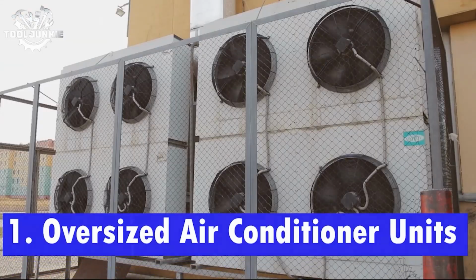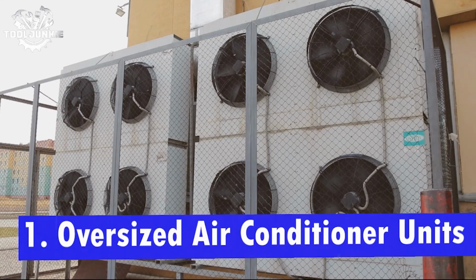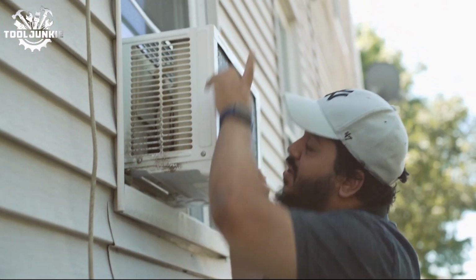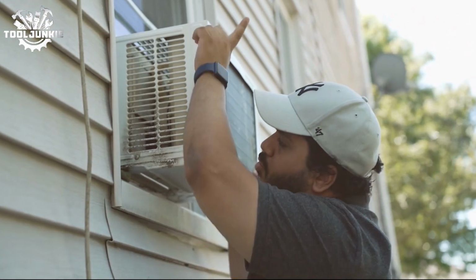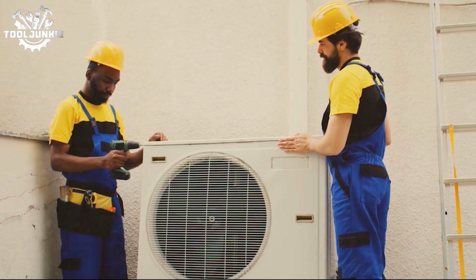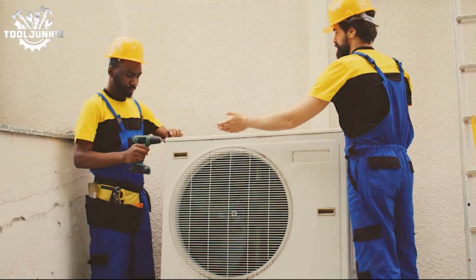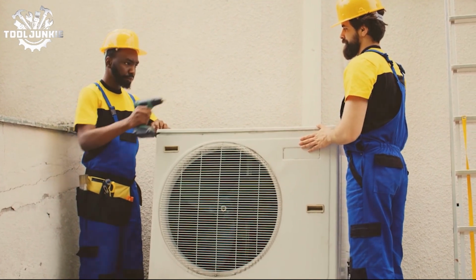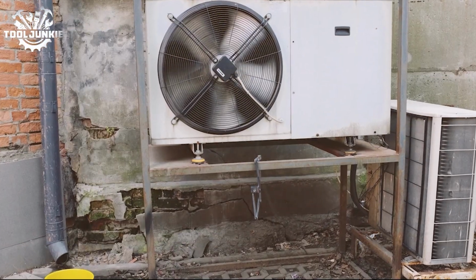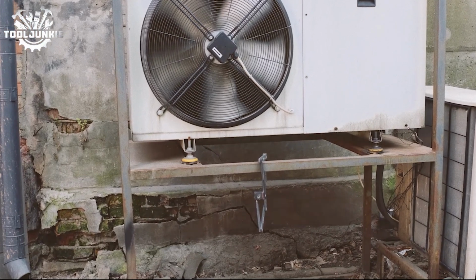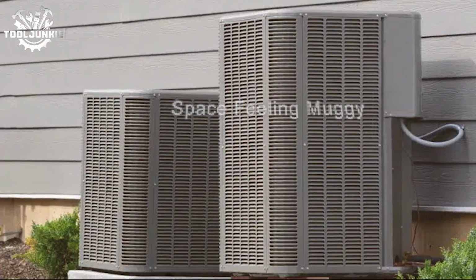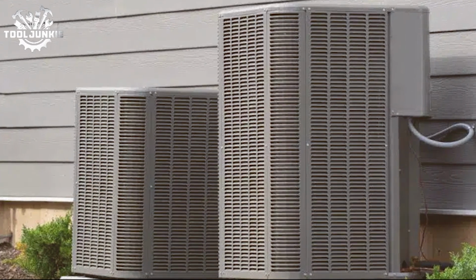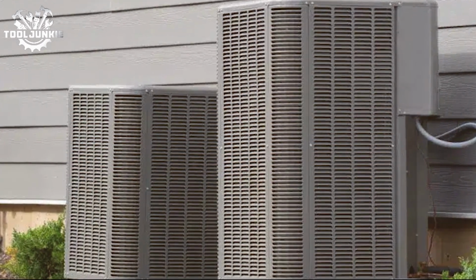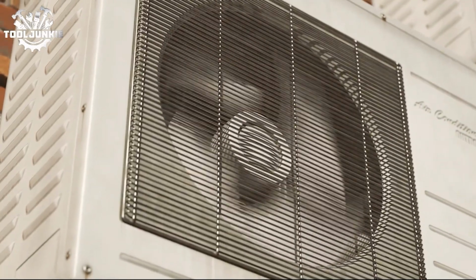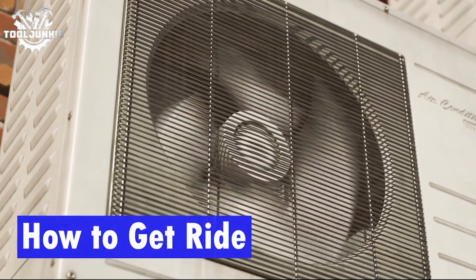Number 1. Oversized air conditioner units. First on our list of usual suspects is the oversized air conditioner. Size matters, and in the case of your AC unit, bigger isn't always better. An oversized unit can cool your room rapidly, but in doing so, it doesn't run long enough to dehumidify the air, which can leave your space feeling muggy. It also means the unit is frequently turning on and off, which is highly inefficient and can lead to wear and tear over time. So how can we get rid of the problem?